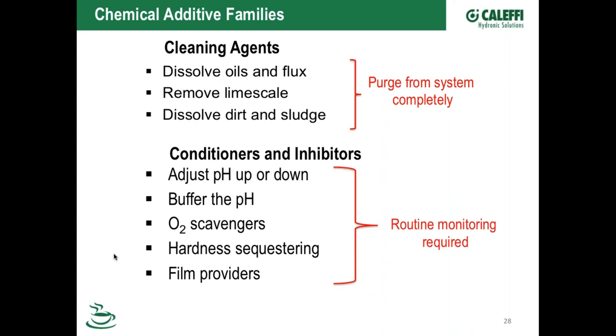So that's kind of what you're getting when you put these inhibitor chemicals in. But now you have to keep checking that. You have to go back every year, every couple years, and check it to make sure you haven't used up or consumed these different ingredients, because then your water is going to go downhill on you again and become aggressive again. So basically what you started now is a chemical romance. Once you put those in there, you got to go back, check them from time to time, you might have to boost them. And in the case of glycol that gets really bad, you're going to have to take it out and start over because you can't fix or salvage it. So just learn what you need to do to test that.